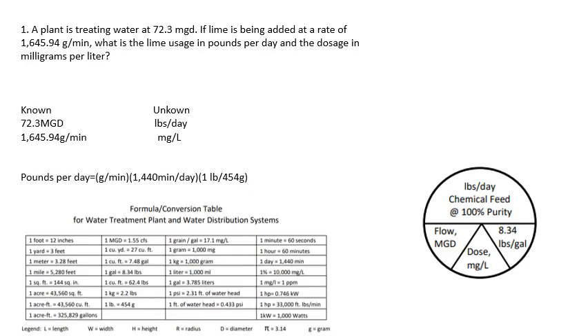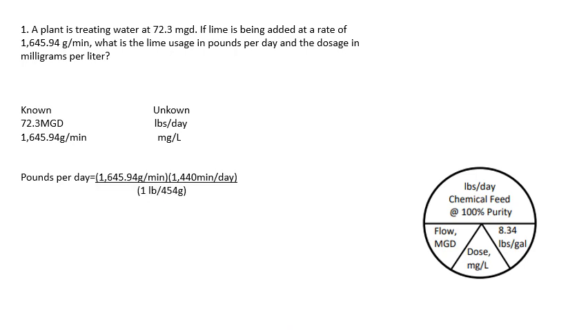Pounds per day is grams per minute times 1,440 minutes in a day, and one pound equals 454 grams — from the Florida distribution and water treatment formula conversion table. So: 1,645.94 grams times 1,440 minutes in a day, then divide by 454 grams to cancel units and get pounds. That gives us 5,220.60 pounds per day.